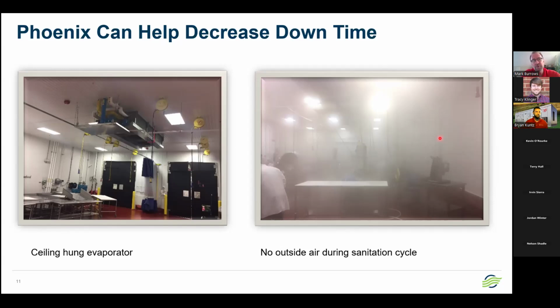Typically speaking, on these evaporators in the room, they don't turn those off, they leave those on, right? So if the suction's 25, let's say 30-degree suction, and that unit is still left running, yes, it's going to condense a lot of moisture on the cooling coil. The problem is once you cross the saturation curve, you will literally see a fog bank on the discharge of that. That's super saturated air. So not only do you have the issue of the fogging effect with the hot water on the cold floor vaporizing, you also have it coming right off the evaporator. And a lot of plants like this, now you're talking OSHA problems, safety issues, and all the rest of that. So to Brian's point, a simple makeup air unit would probably definitely solve their problem in this scenario. Yep.